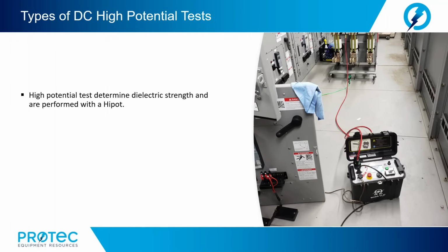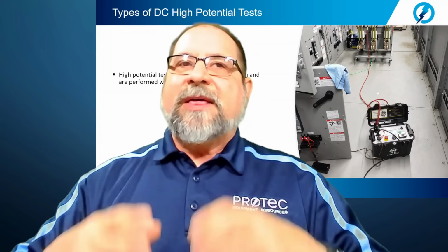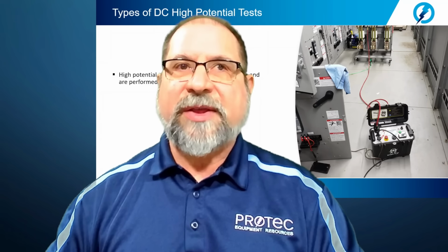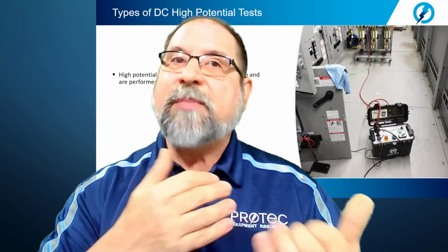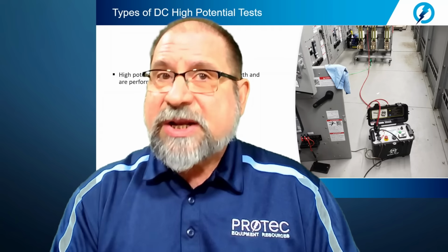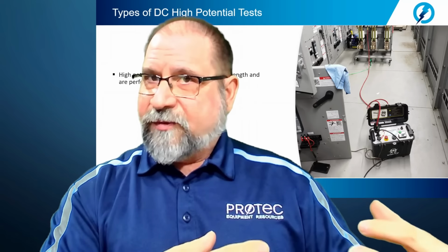All right, now, high potential tests determine dielectric strength and are performed with a high potential test set, or a high pot. Now, DC testing at under voltage levels is also very, very common. And I do want to make a point clear that when we are talking DC potential testing, there is the under voltage DC testing, typically performed with a device called a megohmmeter or insulation resistance test set. These test sets do not produce the ill effects on the service-aged extruded dielectrics that the high potential DC provides. So I do want to make that point clear that low voltage or under voltage DC testing with a megohmmeter insulation resistance test set is typically fine for all insulation specimens.